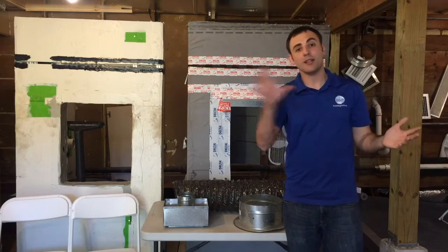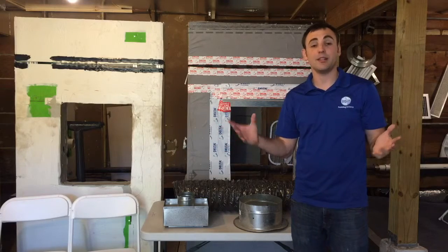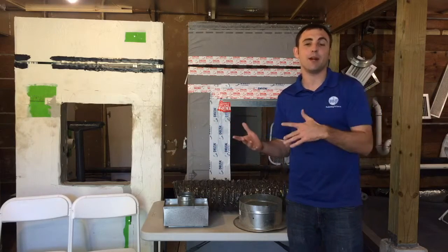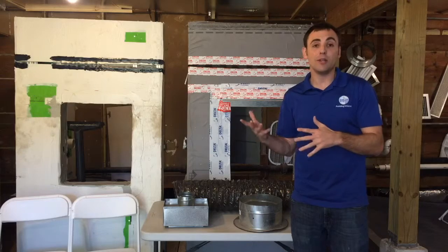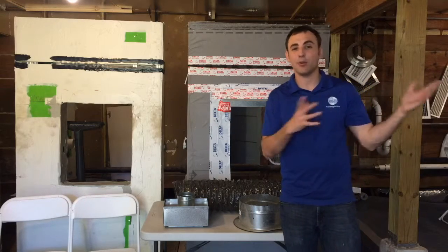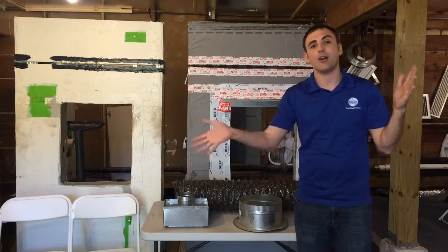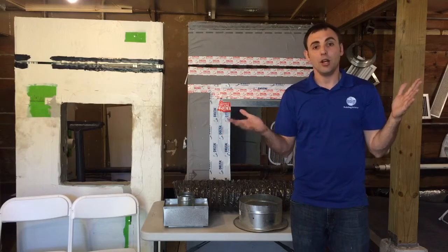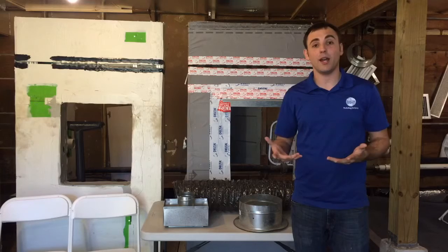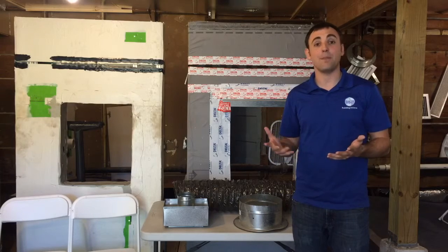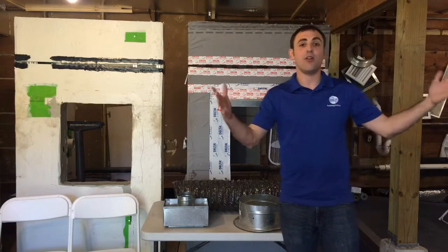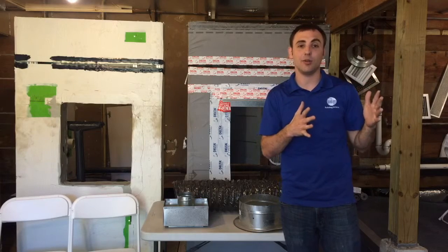So even if you have the right duct size going someplace, it doesn't mean that you're going to get exactly the right amount of airflow to that room, which means that you need to install a series of dampers in some places to shut the air off in one place so you can push that air to another place that needs it more. And there's a whole bunch of different ways to damper a system. The best way to do it is as far back, closest to the system, as you can get.